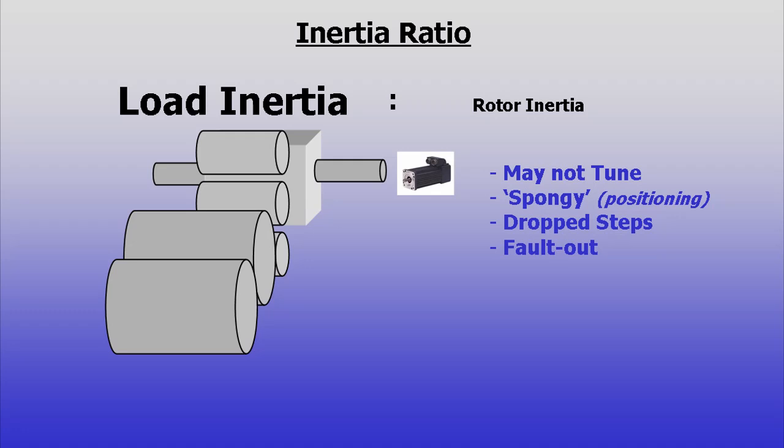If the inertia ratio is too high, the system may not tune, might feel spongy, may drop steps or simply fault on desired moves.